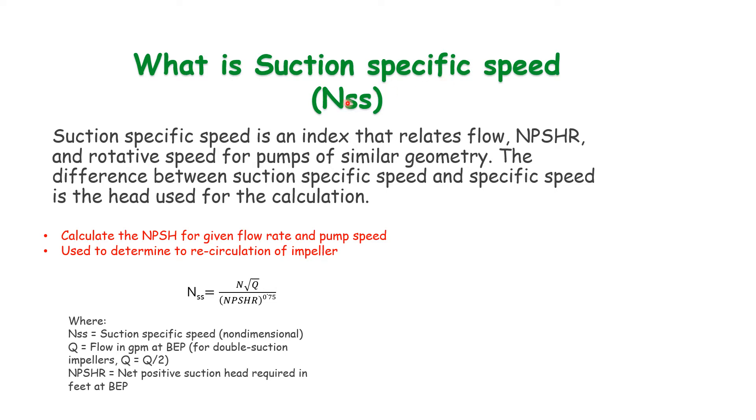What is suction specific speed? It has the abbreviation NSS. Suction specific speed is an index that relates flow, NPSHR, and rotative speed for pumps of similar geometry. It's basically a relationship between three parameters for the pump: flow, NPSHR, and speed.